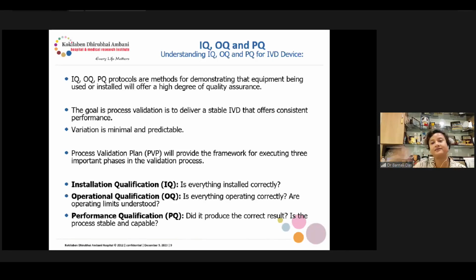If it is a new lab, we can start from design qualification, then shift to installation qualification. When we talk about installation qualification, it should answer: is everything installed correctly? Operational qualification: is everything operating correctly? Are operating limits understood? Then performance qualification: did it produce the correct result? Is the process stable and capable?